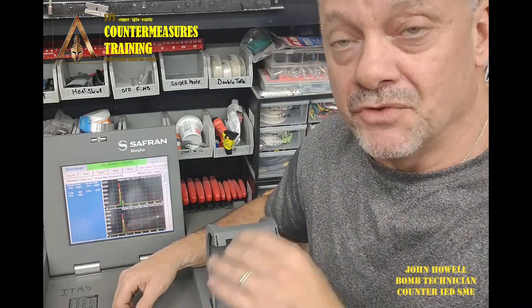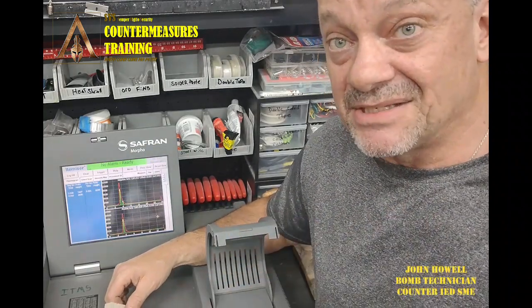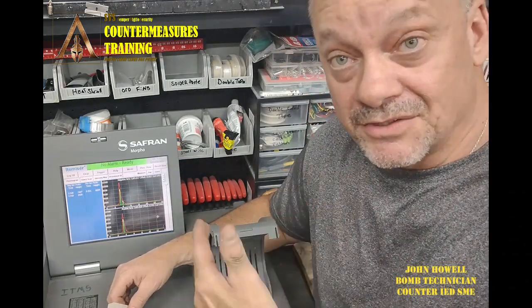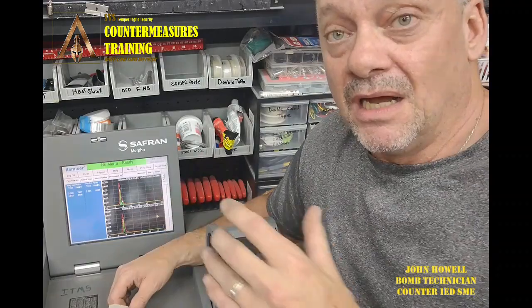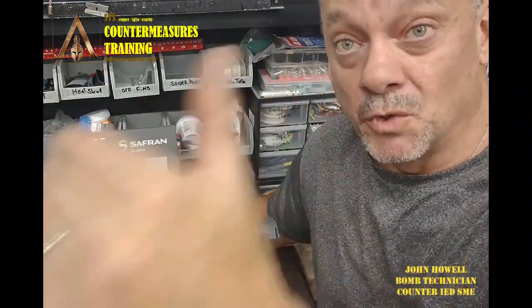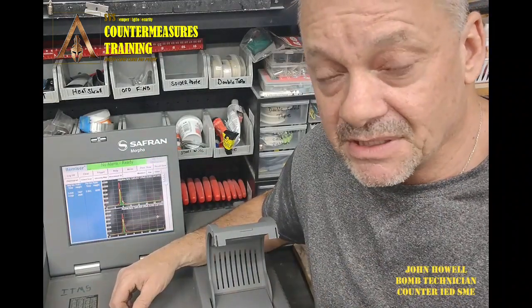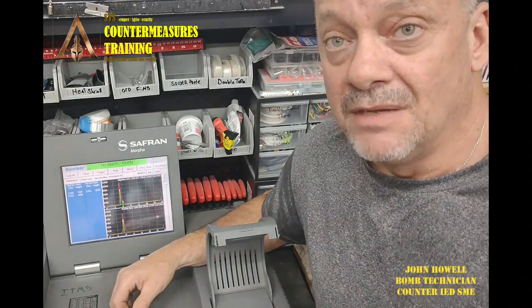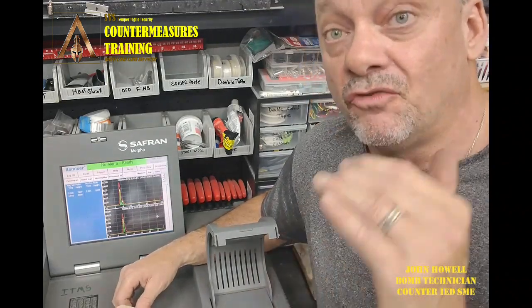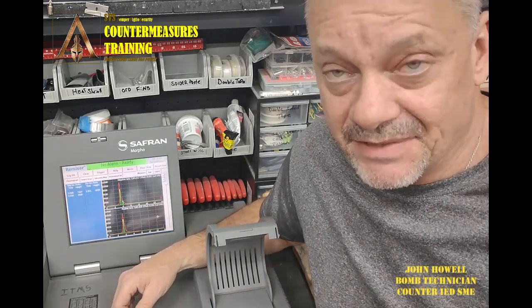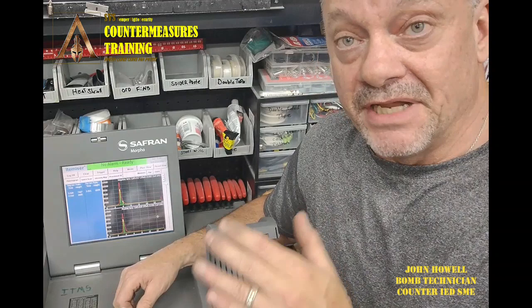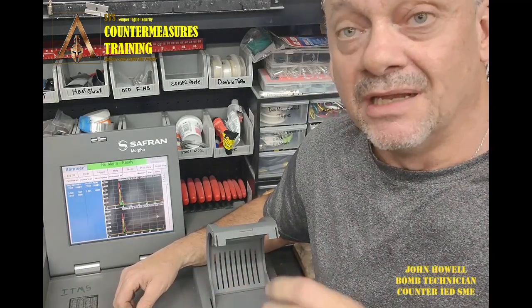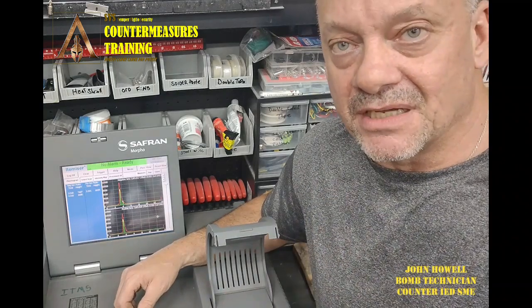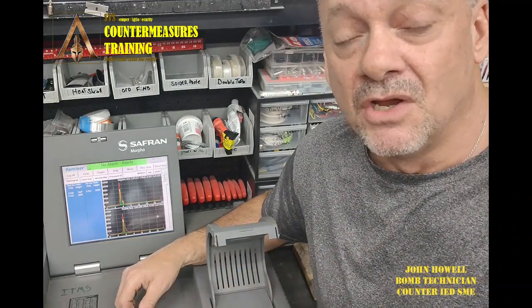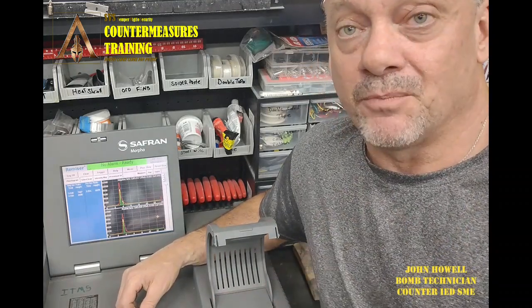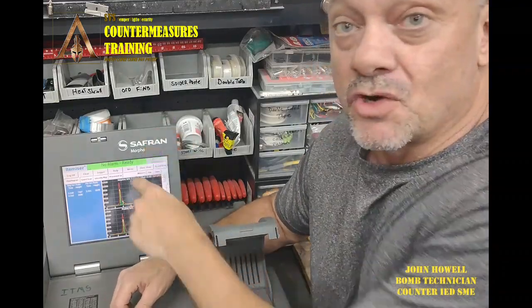And on those modes, you need to be in the mode that optimizes the temperatures, especially in the desorber, and also it changes the temperature in the drift tube if you go to a narcotics detection or a dual mode detection. So if you're looking for explosives, you have to be in the explosive mode because the temperatures have been optimized for explosives, okay? I don't care what system it is, that desorber temp needs to be around 200 to 220. There's been testing and evaluation done. I think in the training you're going to see a paper I reference where they figured out what the optimum desorber temp was for detecting explosives to get the strongest peak height.